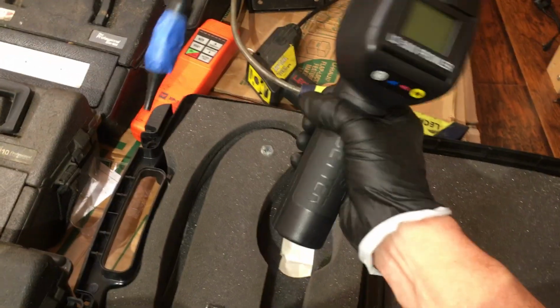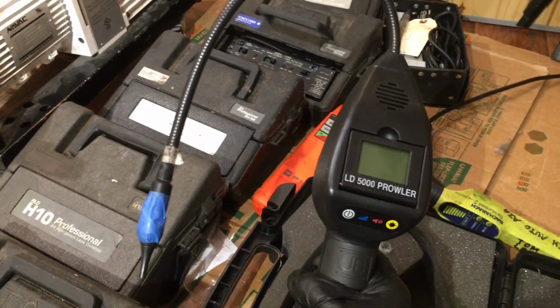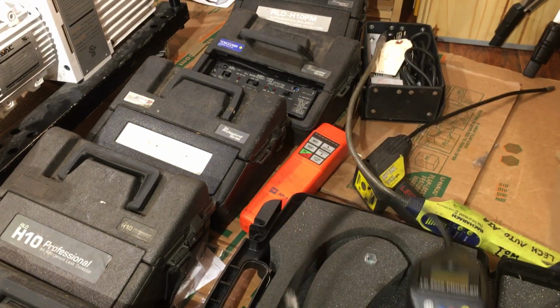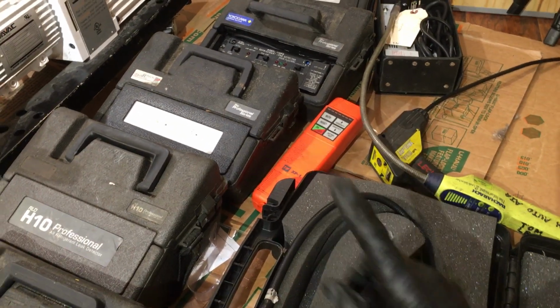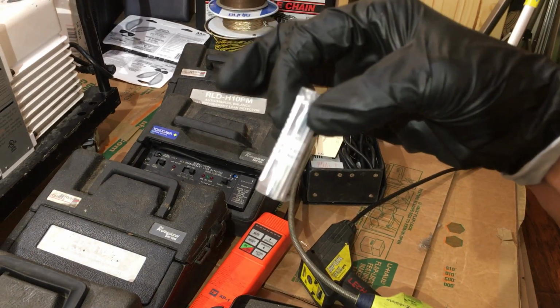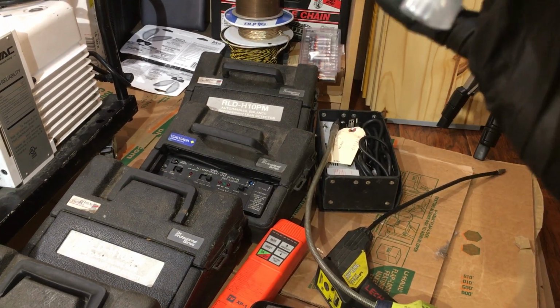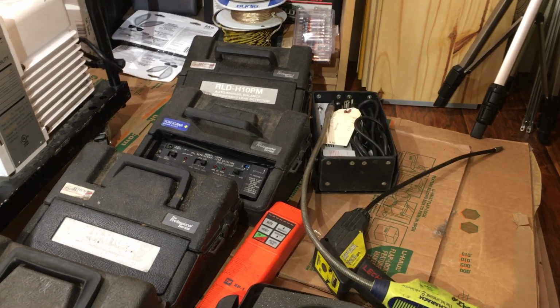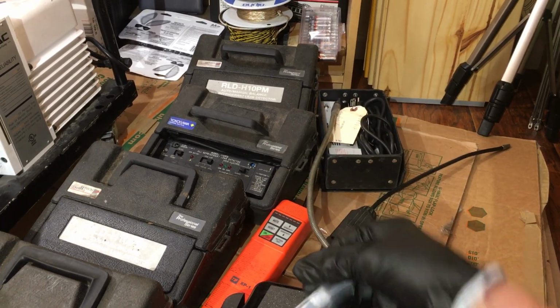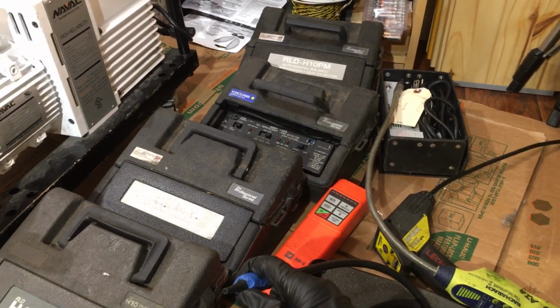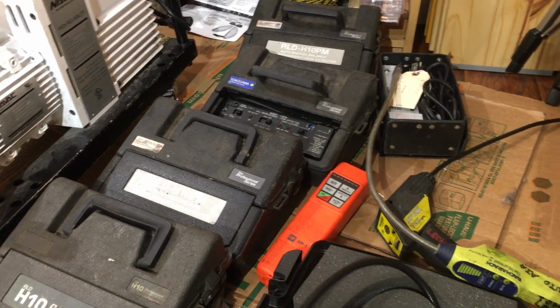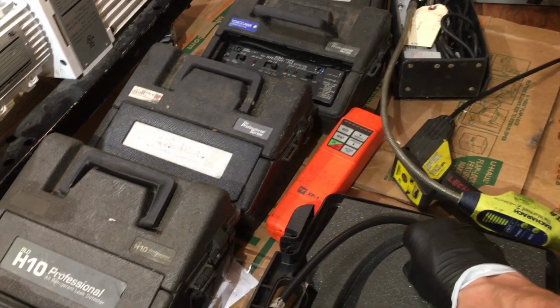The Prowler was much better. This is like $300 something, $400. When they first came out, they were even more. My recommendation for refrigerant leak detectors: only buy refrigerant leak detectors usually, or at least one that comes with a calibration bottle in it. This has a refrigerant in it with a small hole that is calibrated to actually test your sensors. If you can't test them, cracking a bottle and putting the sensor up to the refrigerant is not testing. That doesn't mean it's going to find a small leak.